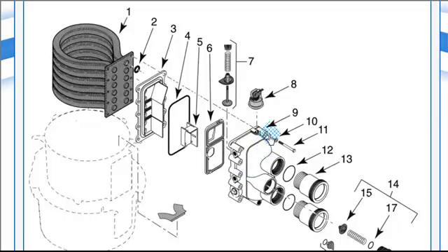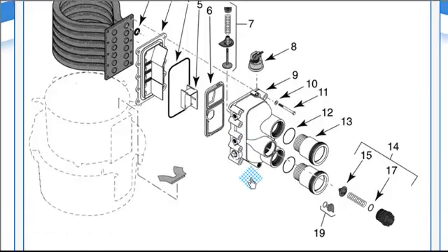And then you torque it on axis. Just don't do one, two, and cock this thing, because you'll break it. All right? The reason why they break, not to repeat myself, is because of cold and dry fire. Usually on this side, it's a big, old, nasty crack. Keep in mind, the O-rings come with the kit. Take off the old O-rings, inspect them, clean up the tubes, put the new ones in, put this in nice and square, and take your time installing it.